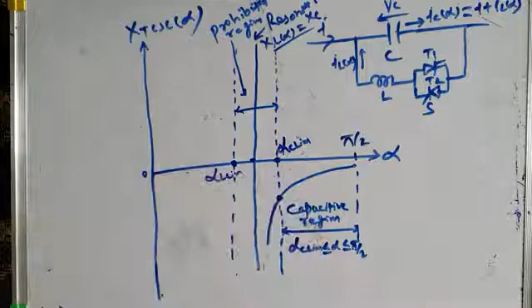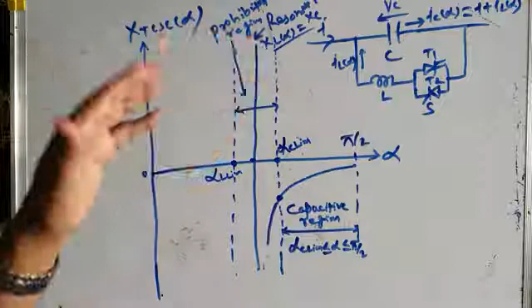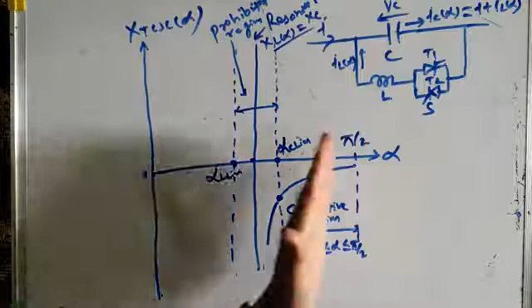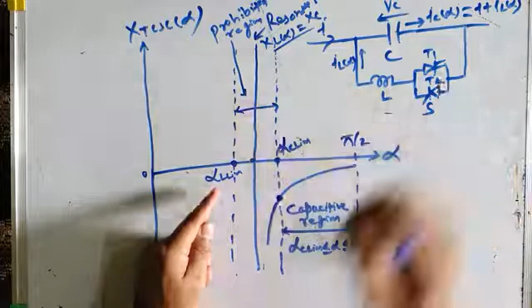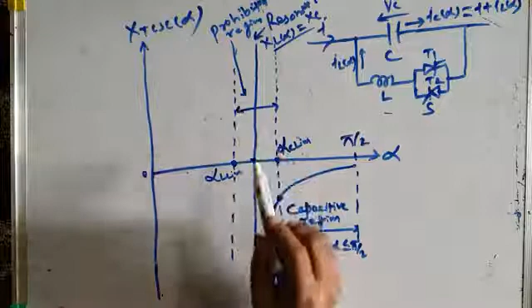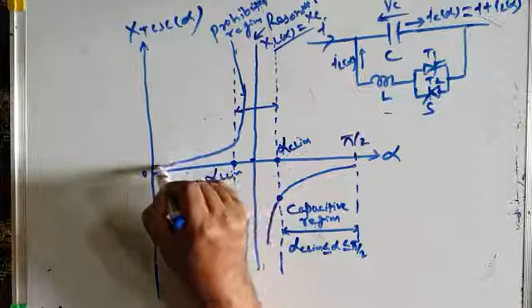If this is alpha C lim, let us call this alpha L lim. Now, if you decrease your alpha below this resonance condition, you go on decreasing alpha, jumping from alpha C lim to alpha L lim. For example, this may be 45 degrees, this may be 50 degrees. Then the TCR reactance will further decrease, and now your circuit, instead of behaving as a capacitive reactance, will have an overall inductive effect. It will behave as an inductive reactance. Within this range the inductive reactance is infinite at first, and then it will go on decreasing till you reach alpha equal to 0 degree.